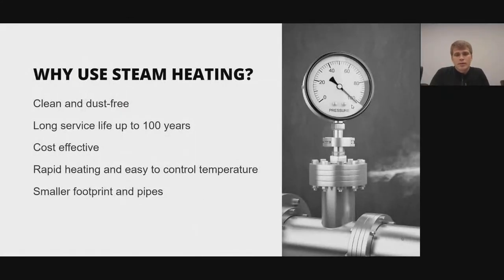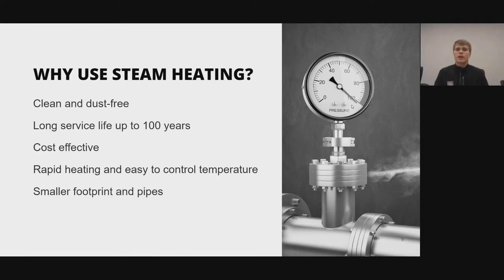Why would we use steam heating? It's clean and dust-free, so you're not blowing air throughout your building — especially relevant with COVID. It has a long service life; if equipment is treated properly, it can easily last in excess of 100 years. It can be a very cost-effective method of heating, especially if you have steam as a byproduct from, say, an electricity plant. Steam heats up much quicker than a hot water system, and it's easy to control temperature by just changing the pressure. Steam can also be compressed, allowing for smaller pipe sizes — especially at higher pressures.